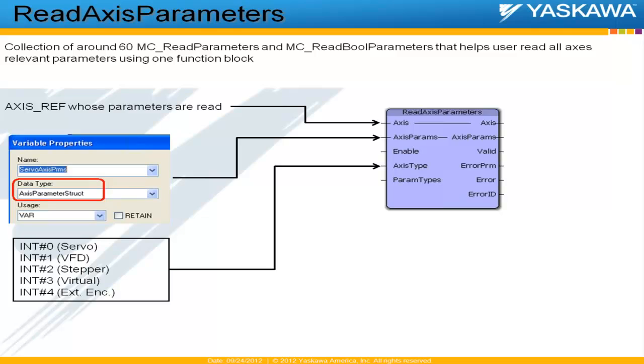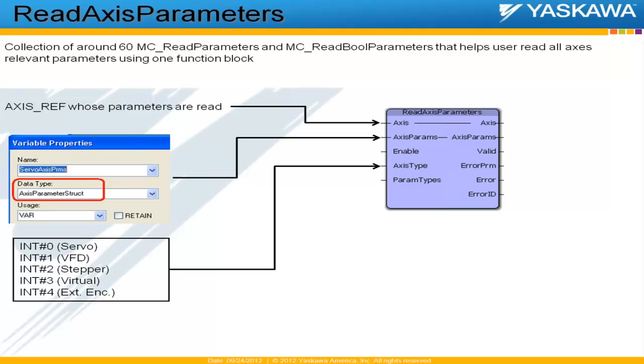So if, for example, the axis that we're trying to read or access is an external encoder, then the code internal to this Read Axis Parameter function block blocks it from reading commanded position or commanded acceleration because these commanded values are not available and would have given us an error if we tried to read commanded position or commanded velocity from an external encoder. So this function block basically prevents a user from wrongly trying to read parameters that are not available for a particular axis. It basically prevents a user from making mistakes or getting errors on trying to read parameters that are not available.